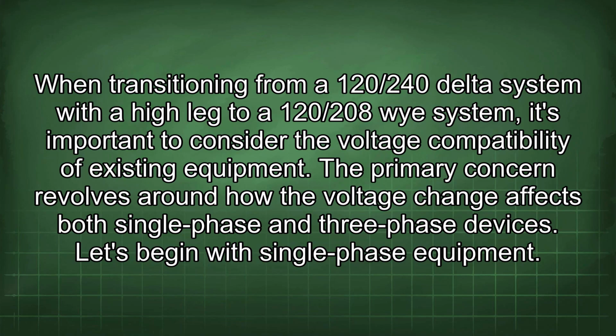When transitioning from a 120/240 delta system with a high leg to a 120/208Y system, it's important to consider the voltage compatibility of existing equipment. The primary concern revolves around how the voltage change affects both single-phase and three-phase devices. Let's begin with single-phase equipment.